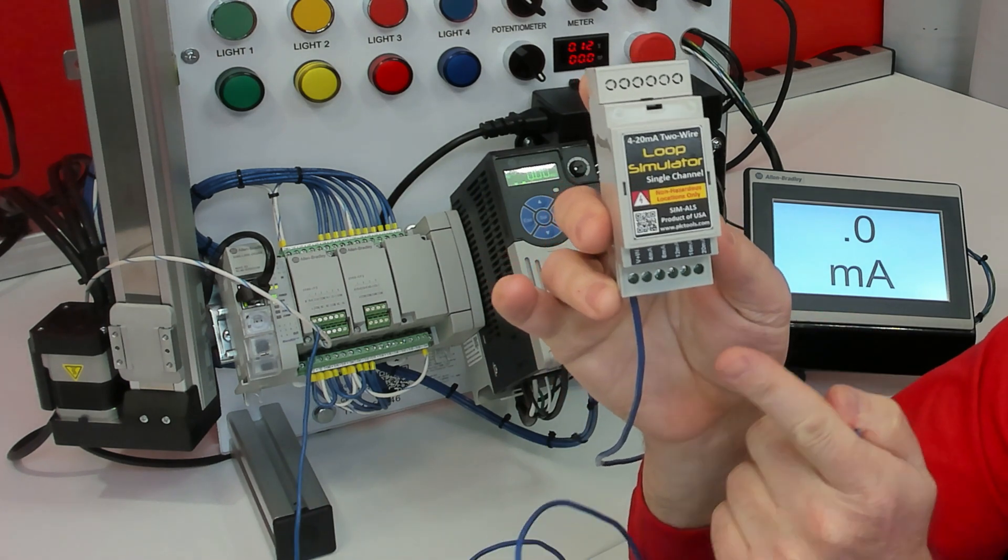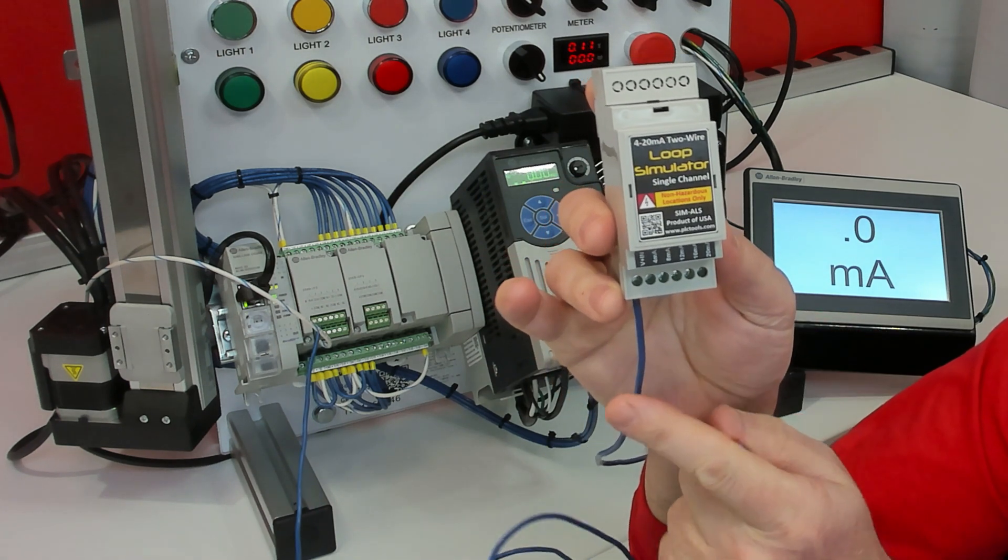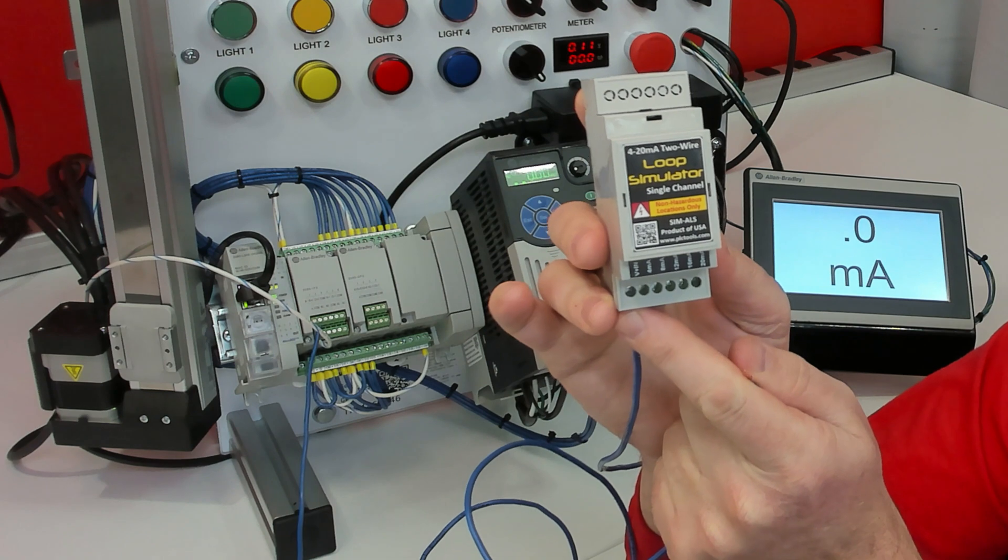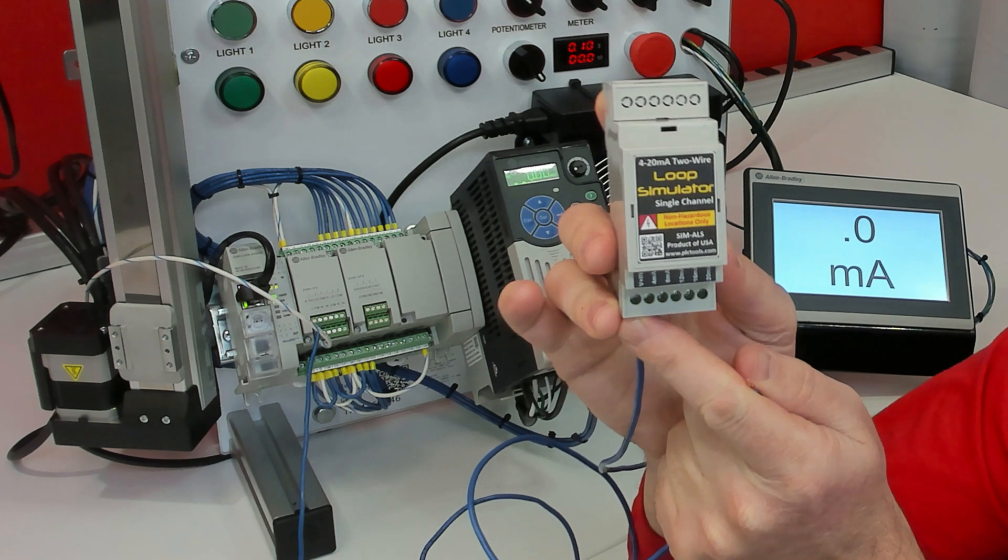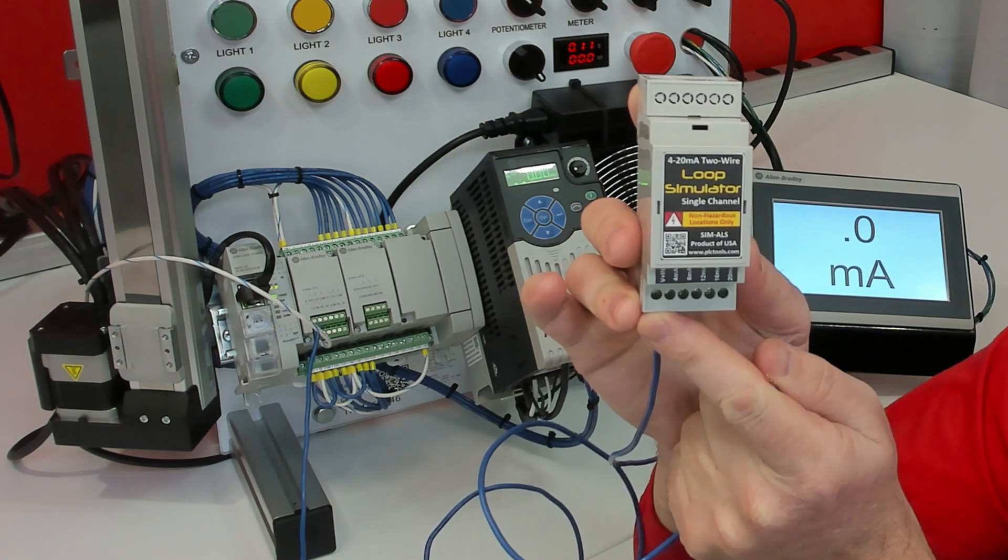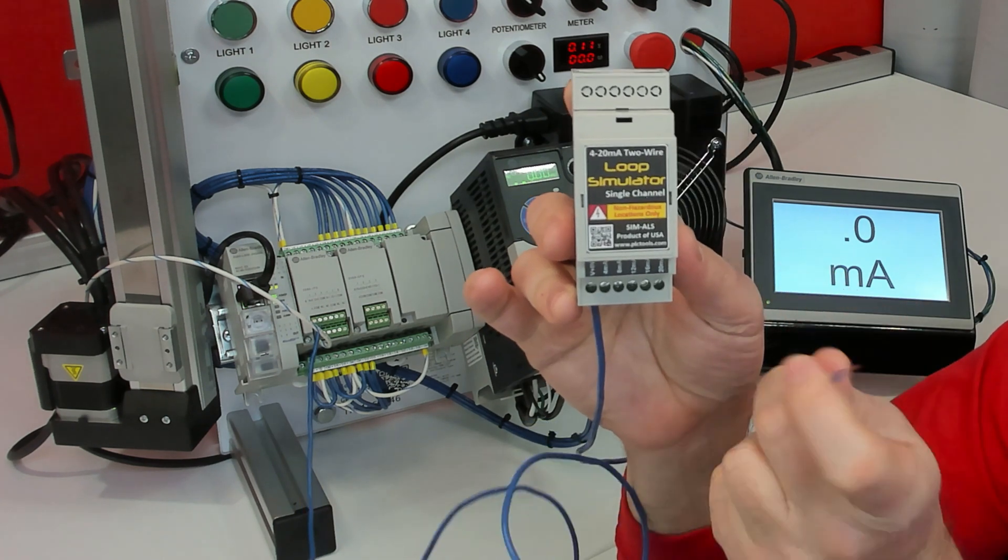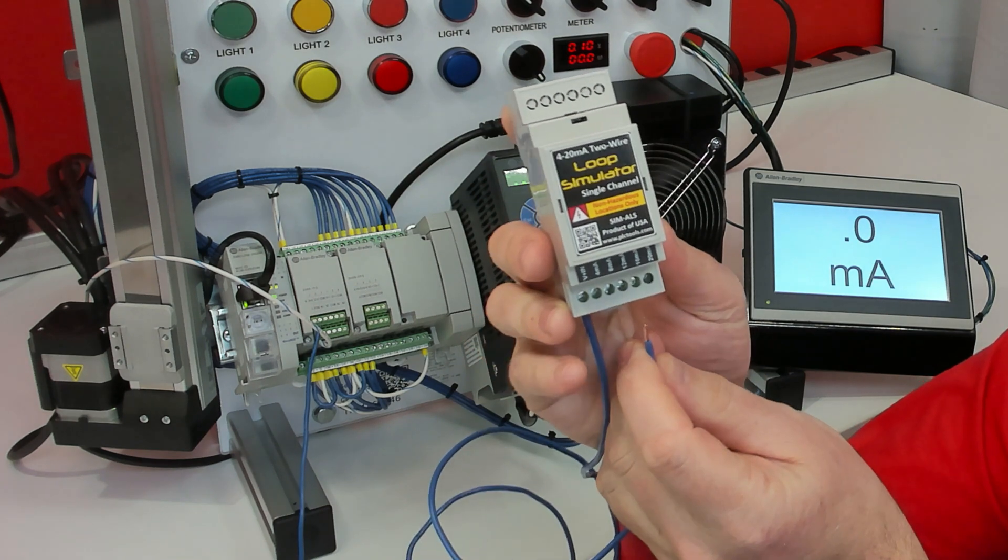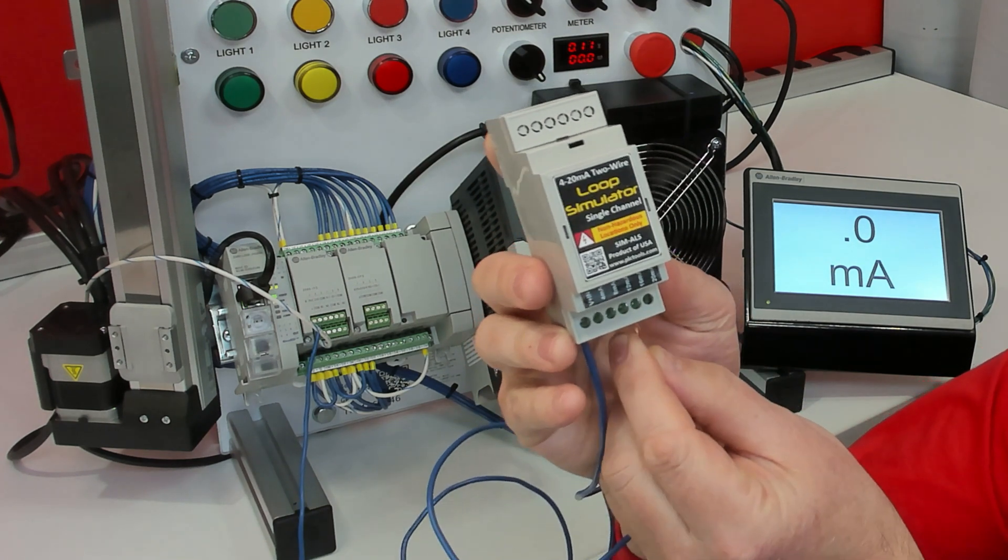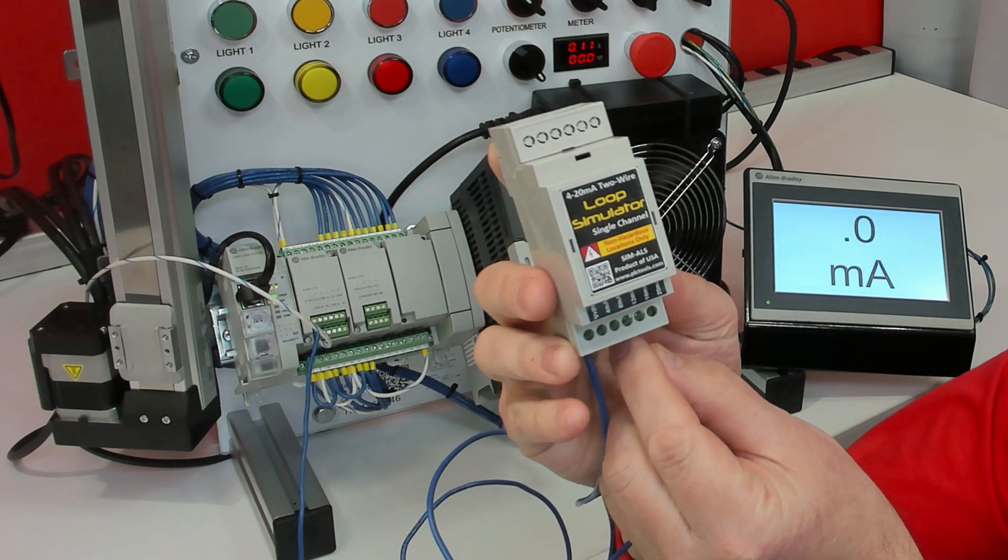So you're going to take plus 24 volt from your 24 volt power supply and connect it to the V plus terminal. And then you'll take your analog input and touch it to whichever terminal that you want to simulate.